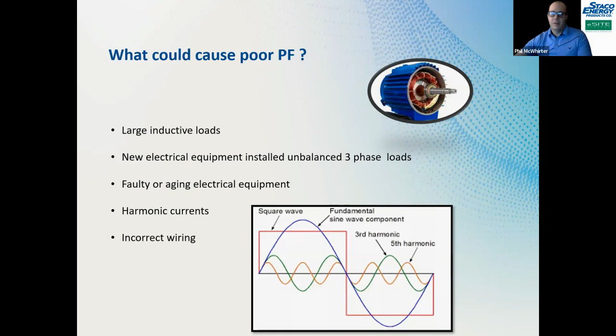If you have too small of a cable on your input to your motors, that could cause poor power factor, because you need more apparent power to drive through the small wire. You're going to have large voltage sags. There are more reasons why you could have poor power factor, but those are the main ones. All right, let's look at the next slide.